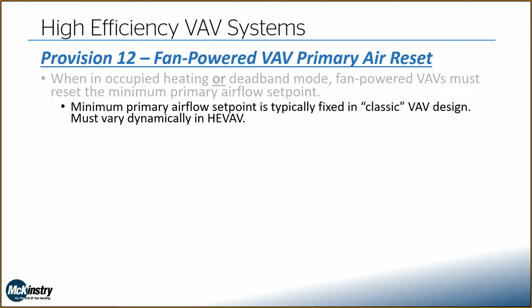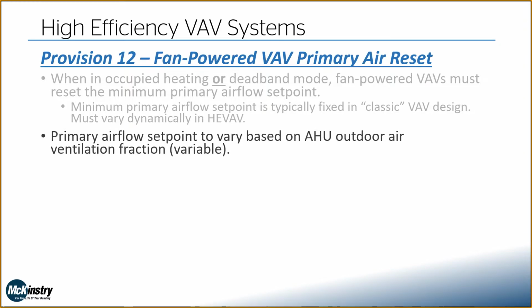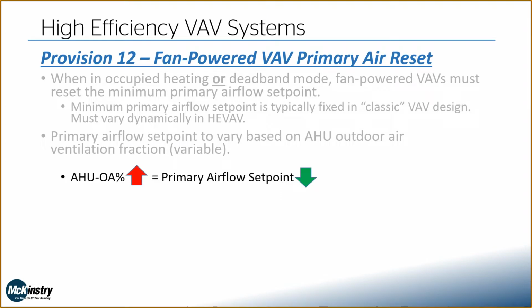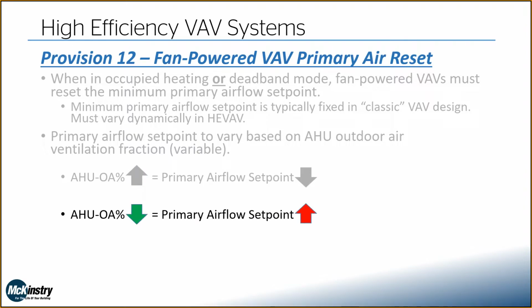But in high efficiency VAV, we have to vary that minimum dynamically. And that needs to vary as a function of the air handler unit outdoor air ventilation fraction. So as our supply fan is ramping up and down, as our outside air damper is opening and closing in response to DCV or ventilation effectiveness, our outdoor air percent at any given time is going to be a variable value. So if our outdoor air percent at the air handler increases, meaning more of our primary airflow is outside air, we can actually drop our primary airflow set point. We're going the other direction. If our outside airflow percent drops, then we have to raise that set point. We have to provide more air to deliver the amount of ventilation air required by ASHRAE 62.1.